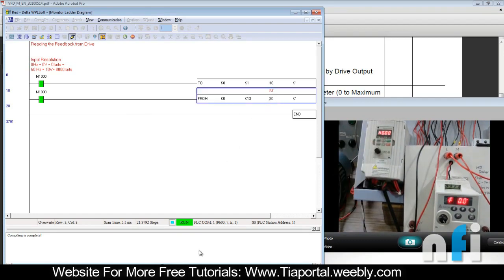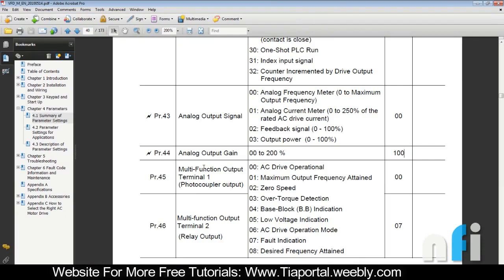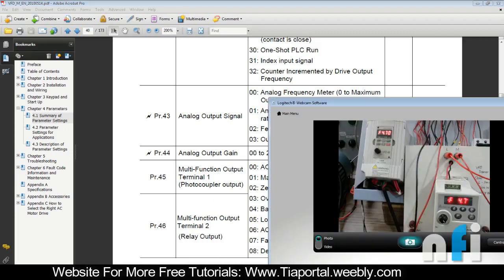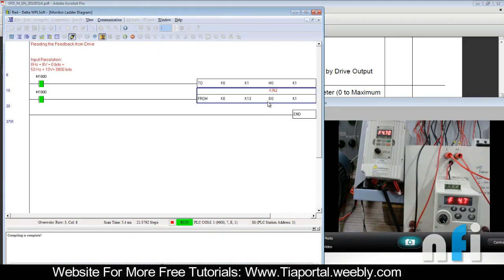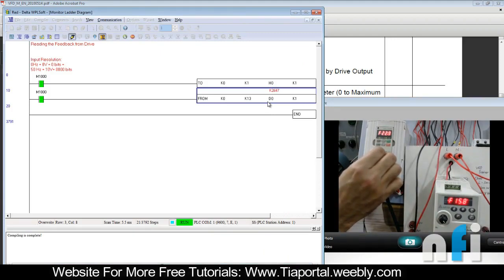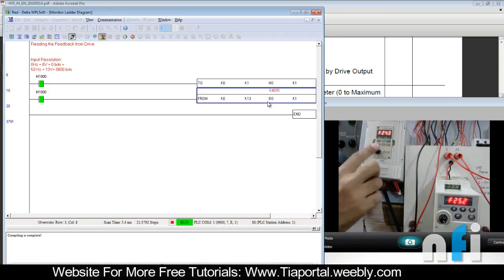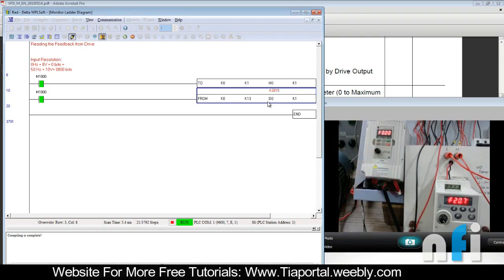Let me roll the gain back to 100% — go to parameter 44 and set it back to 100. Running the drive now: first, the frequencies of master and slave are the same. Second, at 25 Hz the feedback now shows around 4000 bits — that's the one-to-one ratio gain.